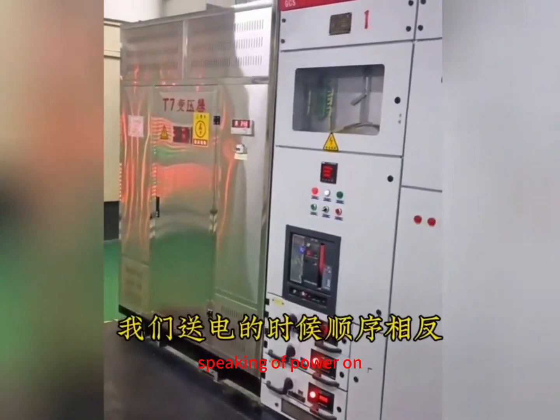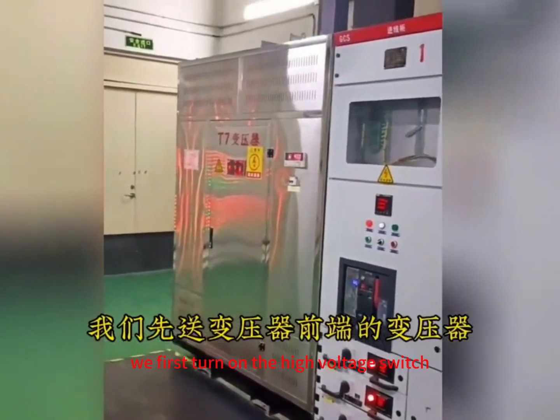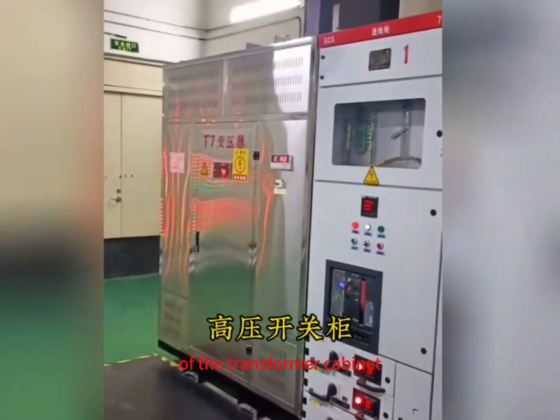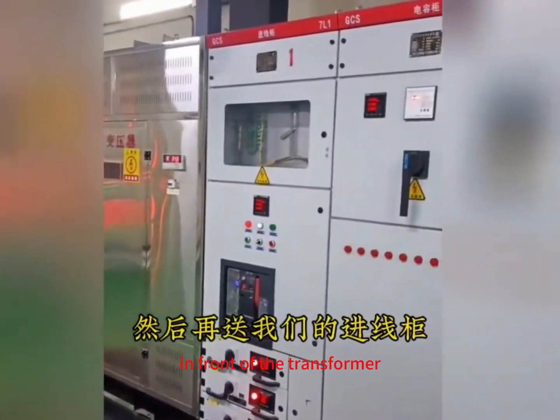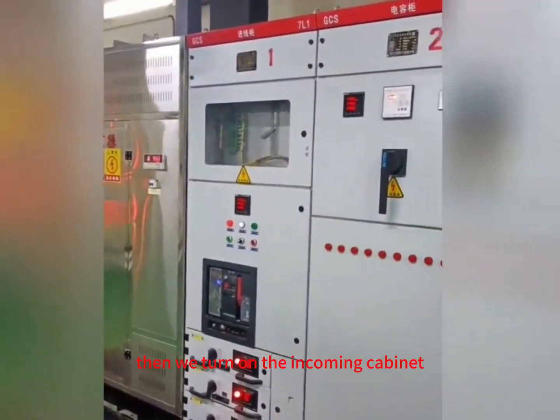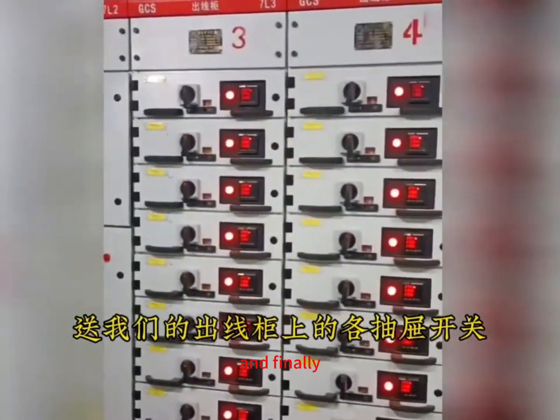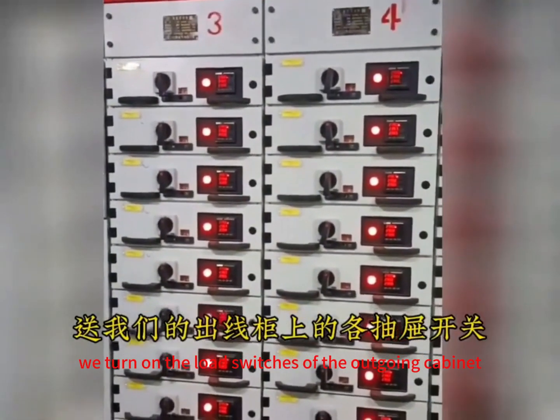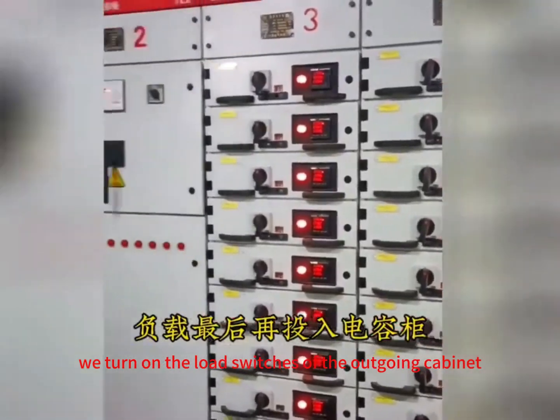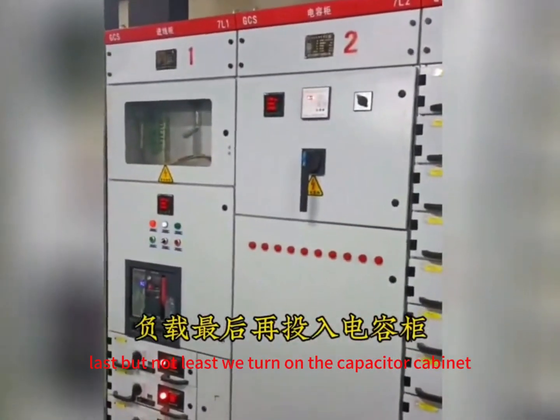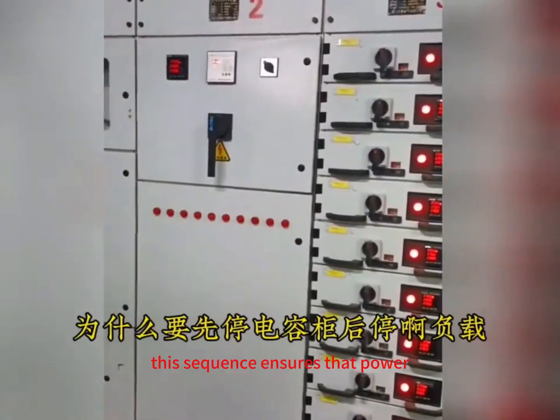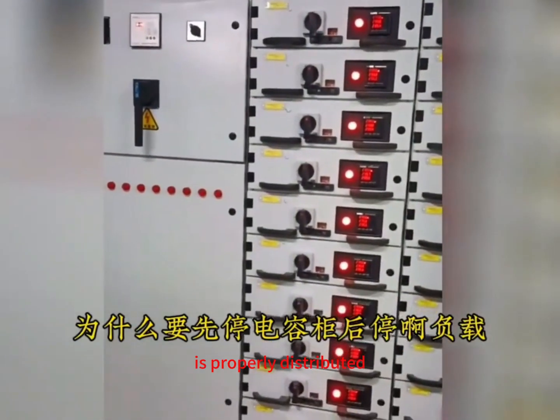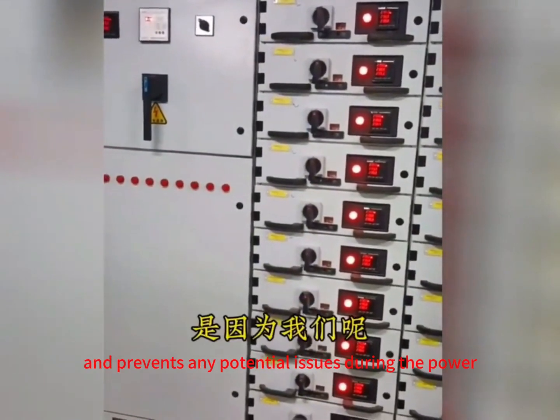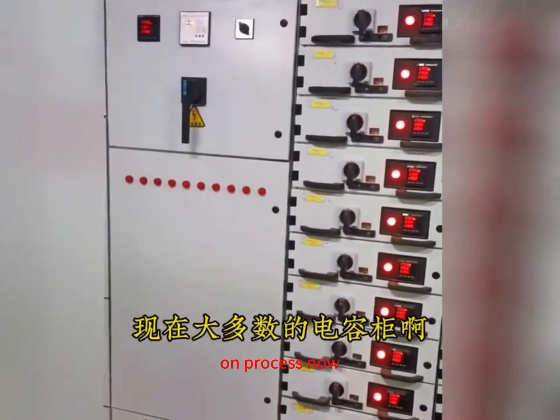Speaking of power on, the sequence is reversed. We first turn on the high voltage switch of the transformer cabinet in front of the transformer, then we turn on the incoming cabinet, and finally, we turn on the load switches of the outgoing cabinet. Last but not least, we turn on the capacitor cabinet. This sequence ensures that power is properly distributed and prevents any potential issues during the power on process.